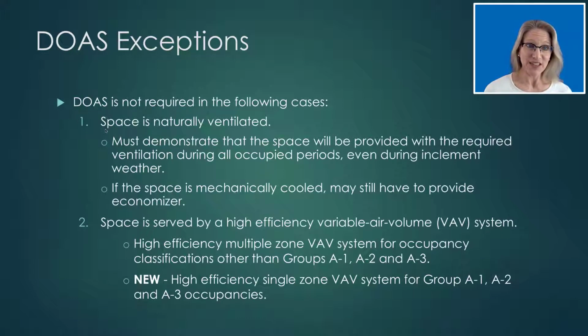And then there is the exception to DOAS if the alternative system that's being put in meets the high efficiency variable air volume requirements. Now, this part has changed a little bit in the 2018 code. There are now 2 high efficiency options. So for high efficiency multiple zone VAV, those systems, if they serve occupancy classifications other than group A1, A2, and A3, can be applied in lieu of complying with the DOAS requirement. And then for group A1, A2, and A3 occupancies, you can utilize the new high efficiency single zone VAV system provision. So you can do that in lieu of DOAS.